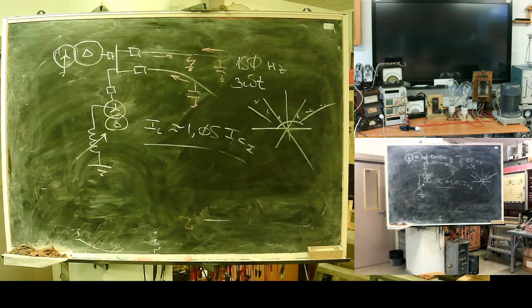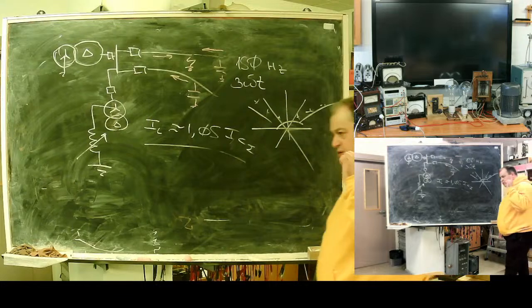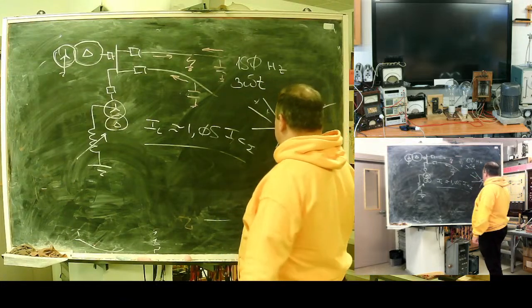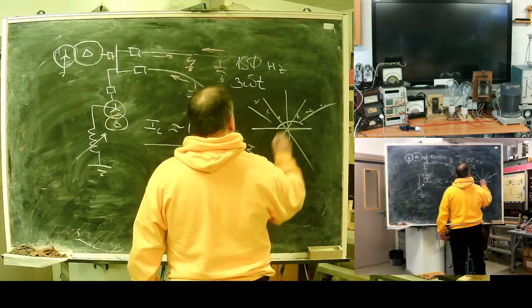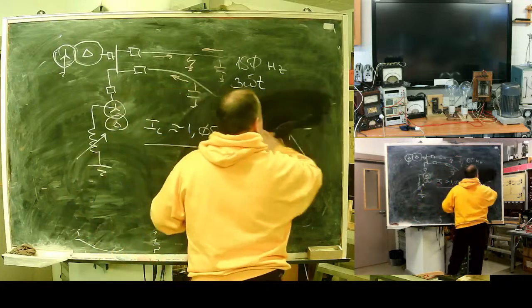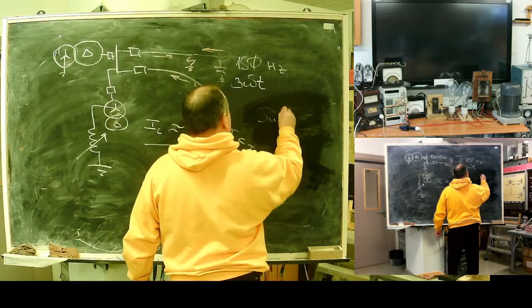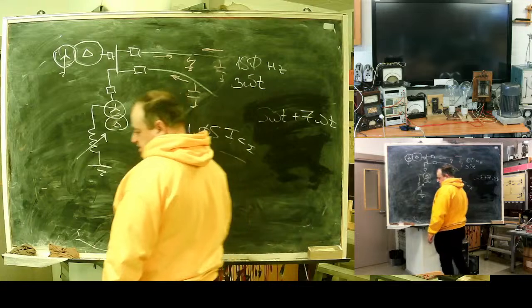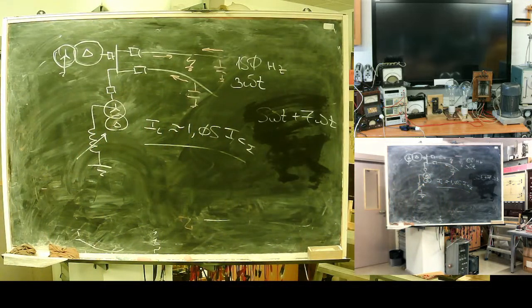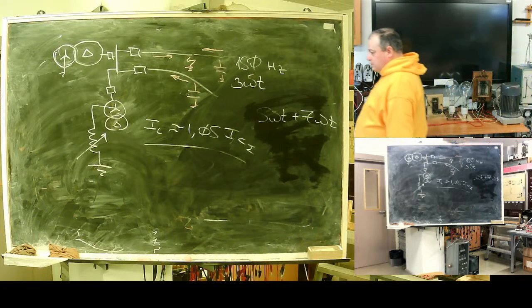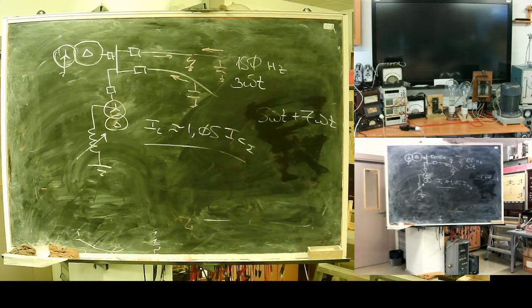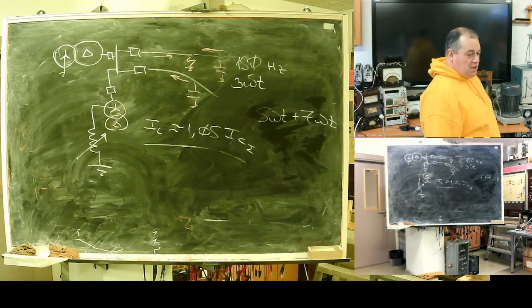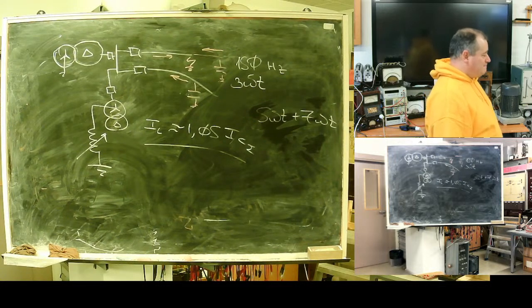Anyway, you should understand that if we deal with a compensated network, simple directed protection is unreliable. On the market there are designs for third harmonic, and there can be designs using 5ω plus 7ω, something like this, designs on higher frequency. Again, not 100% reliable. Much depends on higher harmonics level in your network. In industrial areas, they work. In some rural areas, no.